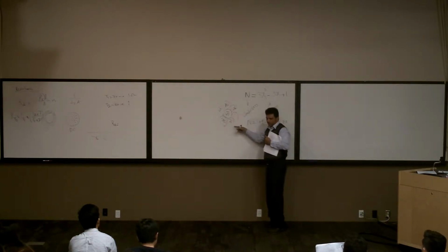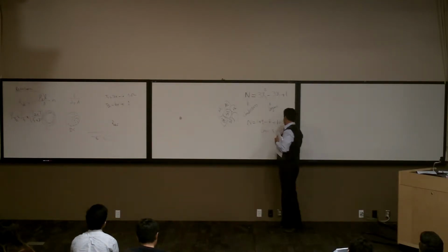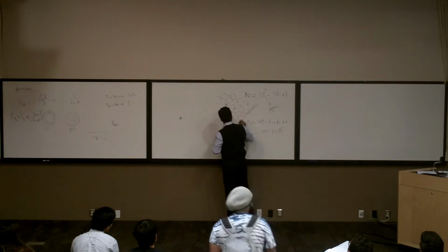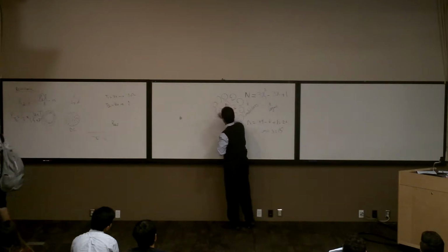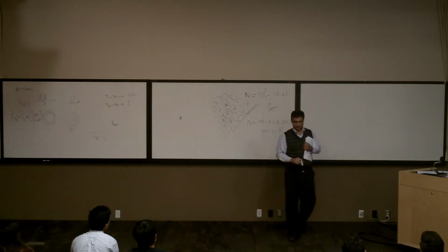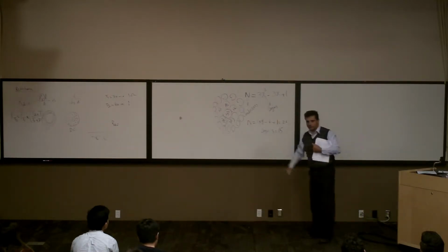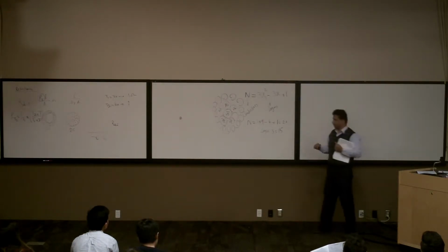Already we have 7 here, right? So it's going to be how much for layer 3? Layer 3 is going to be 22 minus 7, which is 15, right? You should put 15 here, as the number of conductors for that layer. You can see that this one is getting bigger and bigger. The more layers, the bigger it gets.